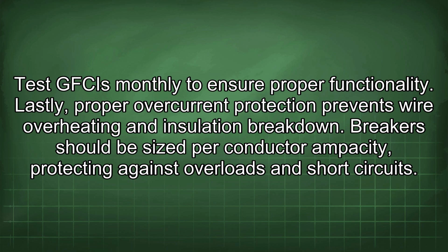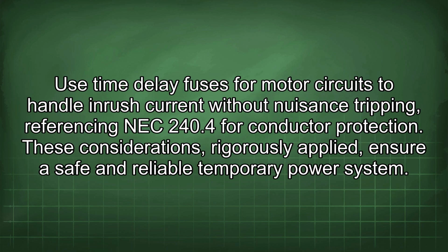Lastly, proper overcurrent protection prevents wire overheating and insulation breakdown. Breakers should be sized per conductor ampacity, protecting against overloads and short circuits. Use time delay fuses for motor circuits to handle inrush current without nuisance tripping, referencing NEC 240.4 for conductor protection. These considerations, rigorously applied, ensure a safe and reliable temporary power system.